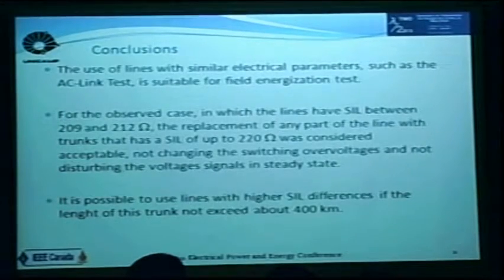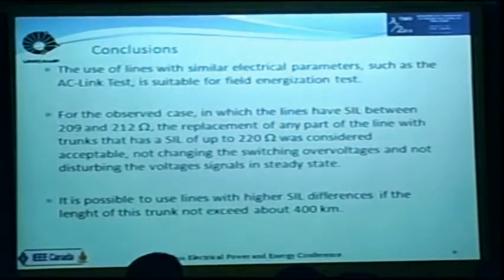So with close characteristic impedance, the main conclusion is that if we use similar electric lines, the link test is going to represent the half-wave line for an energization maneuver. In this case, we have a small difference of about 5%. This does not compromise the result. Higher values would compromise them. So I cannot go further than 10-15% of impedance of positive sequence.